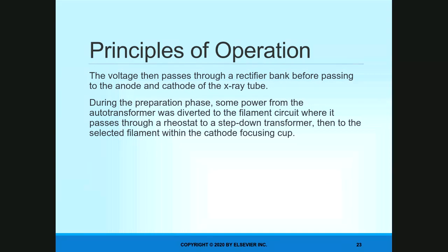Because that cathode is always negative and the anode is always positive, remember, opposites attract. So when that exposure is getting ready to be made, the anode becomes extremely positive, the cathode becomes extremely negative, which means the degree of attraction between them is stronger. Now, what determines how strong the attraction is? Your kVp setting. The higher your kVp, the stronger the degree of attraction.